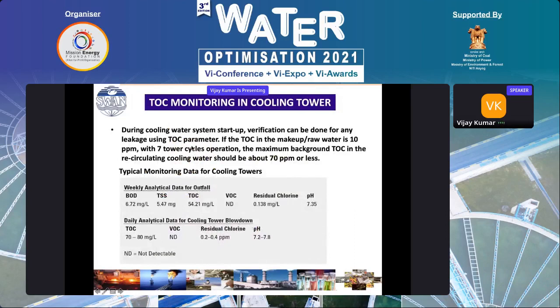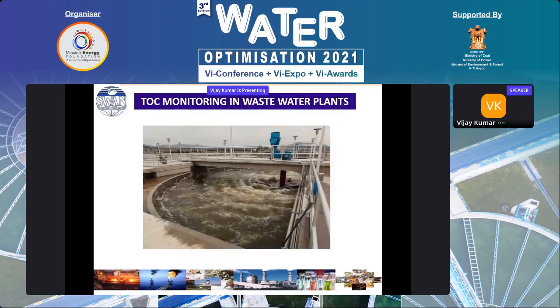There is one interesting article I have seen. If you know the inlet bay TOC and makeup water TOC, say 10 ppm, with 7 tower cycles of operation this goes to almost 70 ppm, where you need to discard this water by bleed down or blow down, and this water has to go for treatment. Otherwise, within no time you have high bacterial growth, and so people also use biocidal chemicals. You can avoid that. If you know your TOC, you can decide how many tower cycles you can pass through, instead of a thumb rule for discarding. This is how you save money.